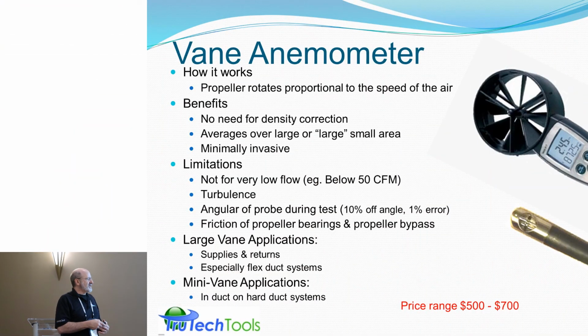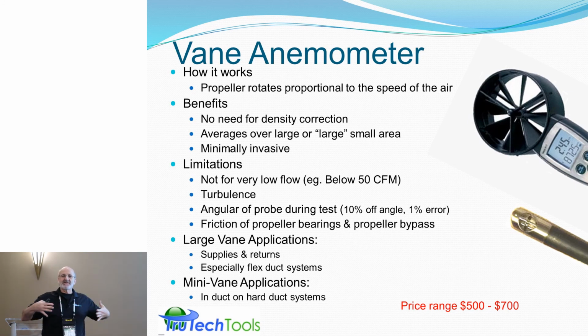For the large vanes, supplies and returns, obviously that doesn't work well in a duct, especially in flex duct systems, in order to get that return airflow where it's hard to make any kind of in-duct measurement. And the mini vane, it's best in hard duct systems to take in-duct measurements. Not so good on supplies and returns, again, because of those vena contracta and the airflows, the air squirts out of the vanes.